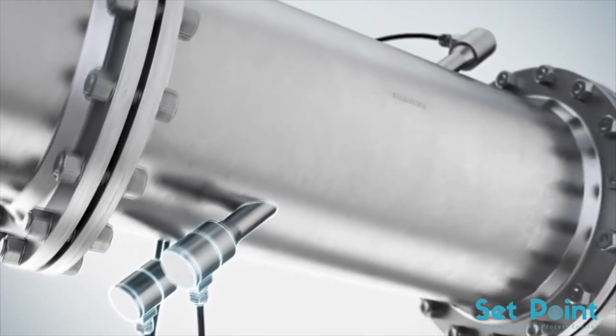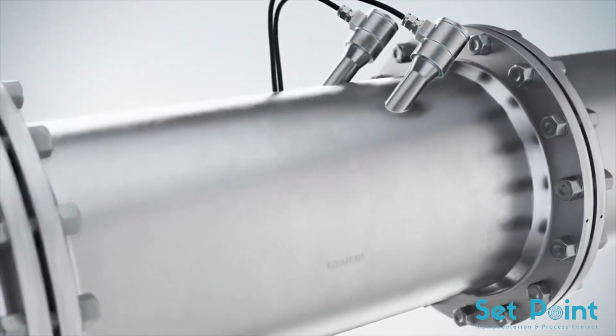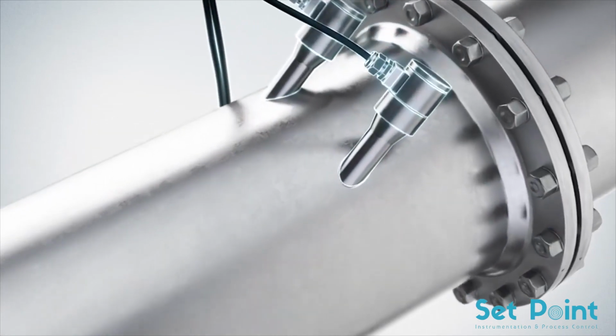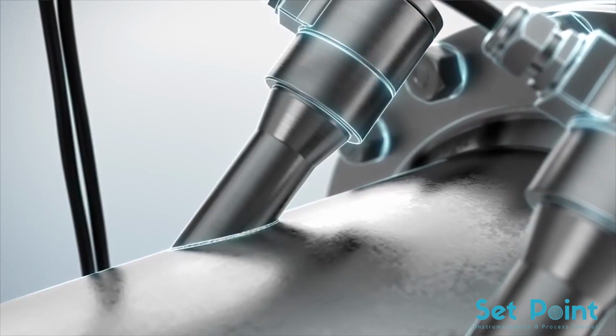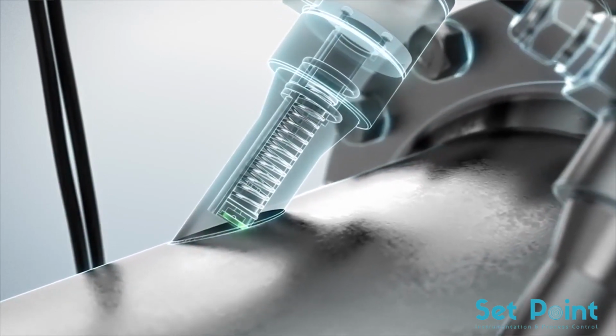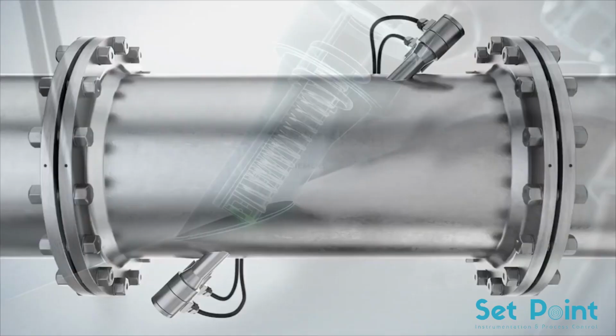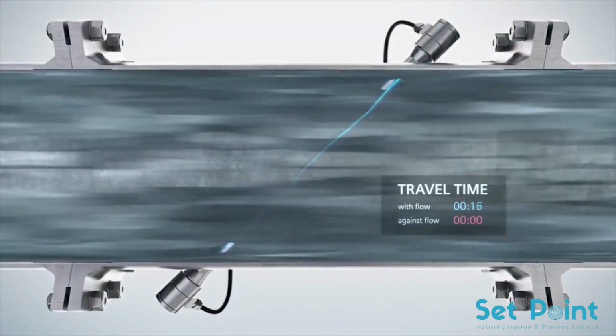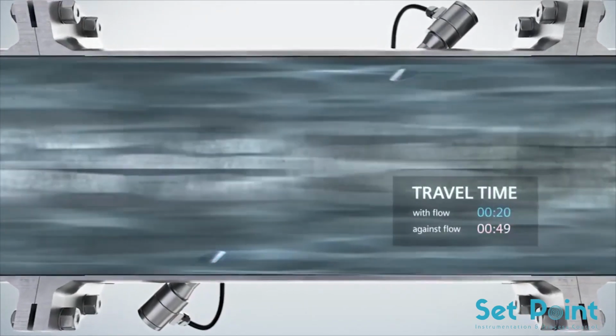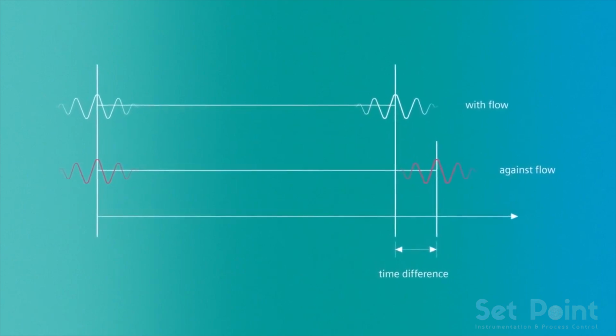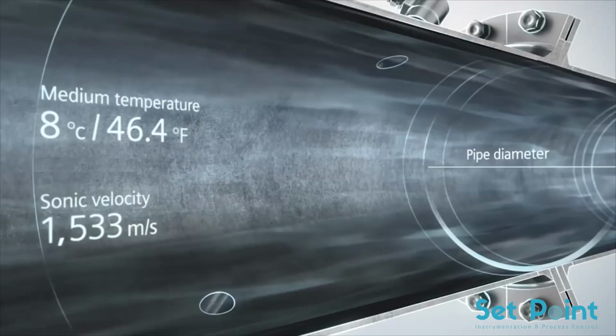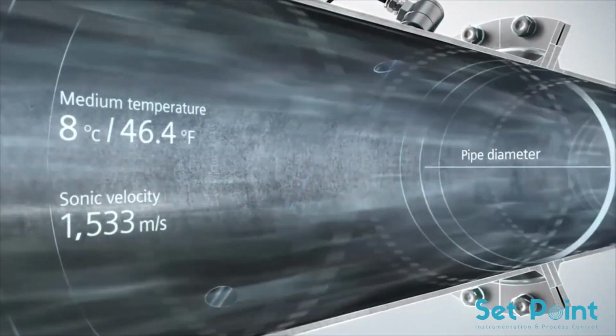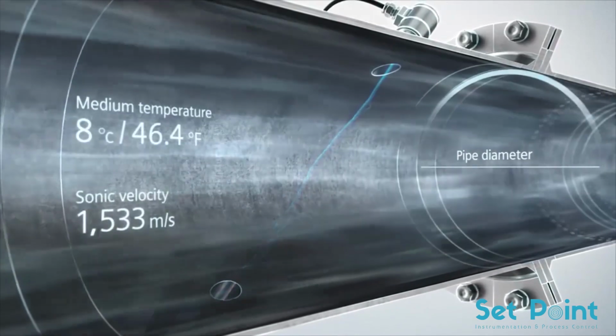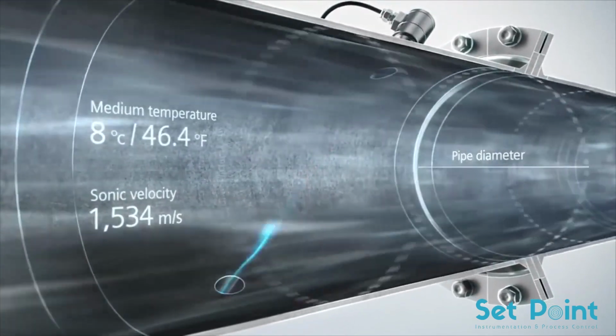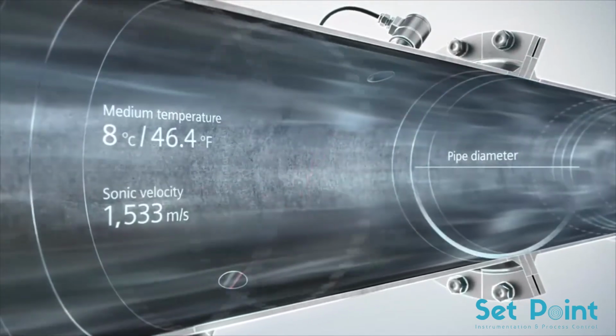Combined ultrasonic transmitters and receivers are placed opposite each other. Ultrasonic waves are alternately sent and received by means of the piezoelectric effect, where mechanical energy is converted into electrical energy through the use of a crystal. When moving in the same direction as the flow, they travel faster than waves traveling against the direction of the flow. The higher the flow velocity of the medium, the greater the difference between the two transit times. Combined with the known area inside the pipe and the measured sonic velocity and temperature of the media, it is possible to accurately measure the volume, and also to derive parameters like density and viscosity.